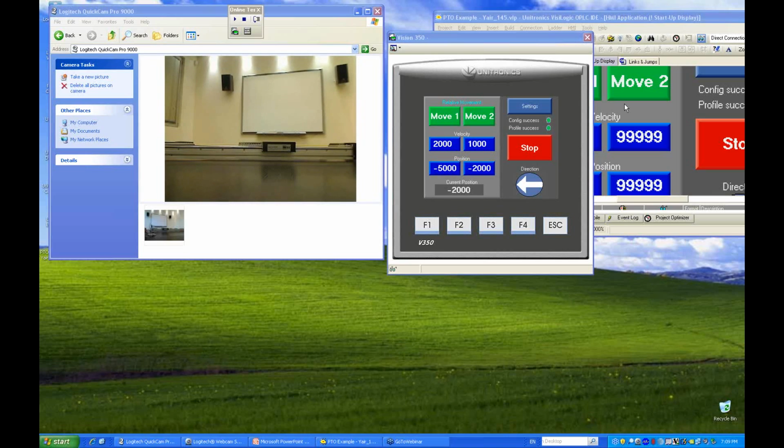Okay. Another question from Mark, following a set speed from an external encoder. The specific function we discuss, the PTO, is open loop. Yair already stated that. I am stating it once again. In general, the function as such has no internal modules or utility to perform that. This can be done anyway, but you need a little help with the ladder.